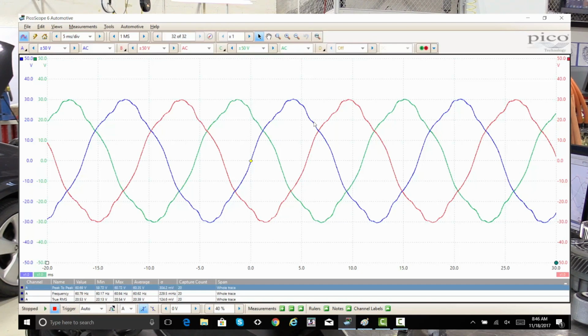Phase relation: the waveform from each of the three phases should be 120 degrees apart. This phase shift creates a rotating magnetic field in the motor. Amplitude: all three waves should have similar amplitude if the motor windings are balanced and the power supply is functioning correctly.